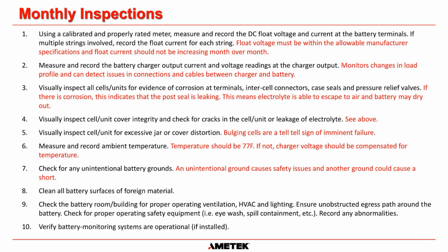Now, for monthly inspections, they're saying that you should use a calibrated and properly rated meter and measure and record the DC float voltage of the battery terminals. Okay. And also record the float current for each string. Now, the float voltage has to be within the range allowed by the manufacturer. Each manufacturer has different specifications for the float voltage depending on temperature.